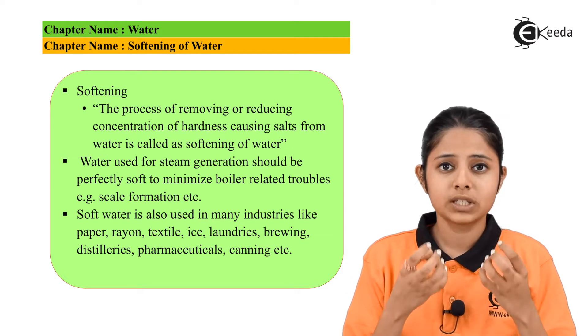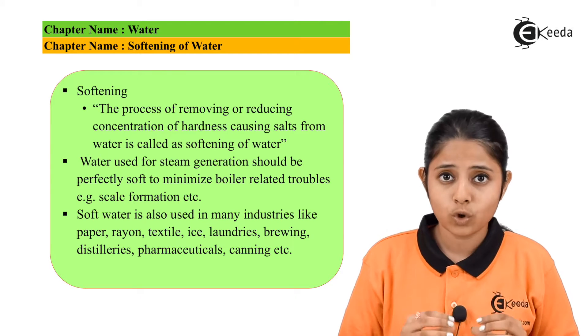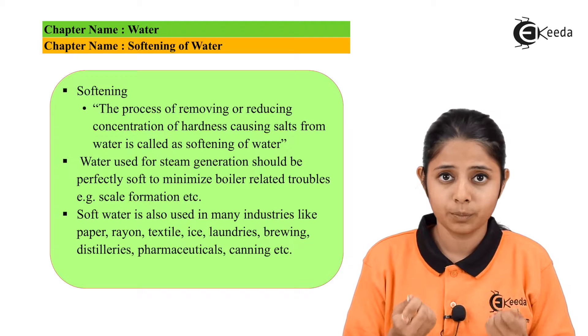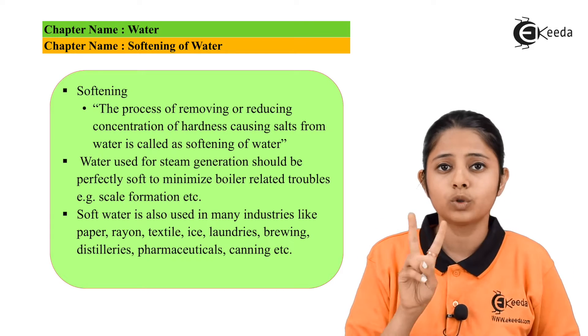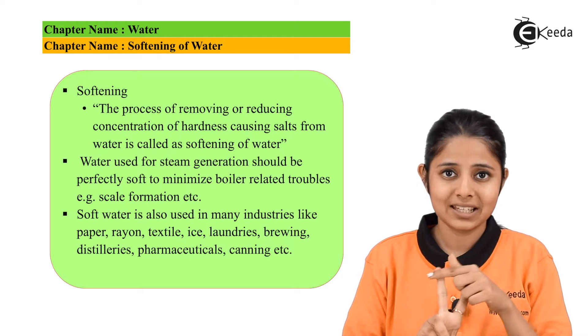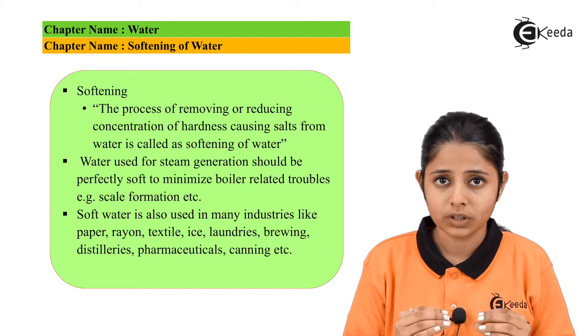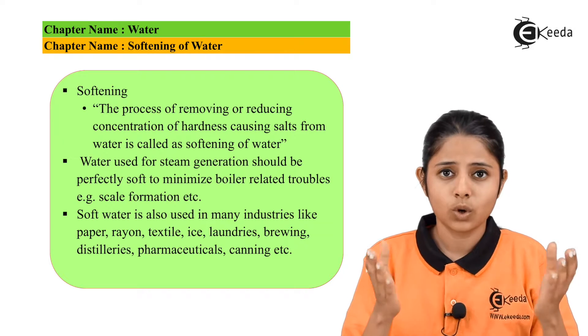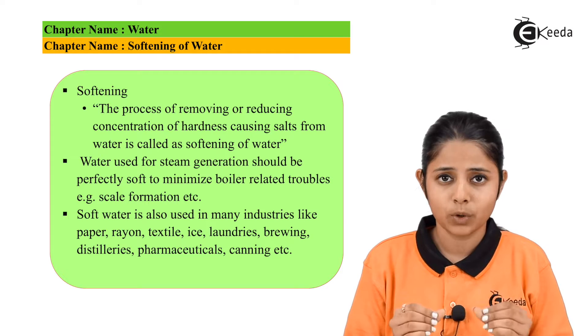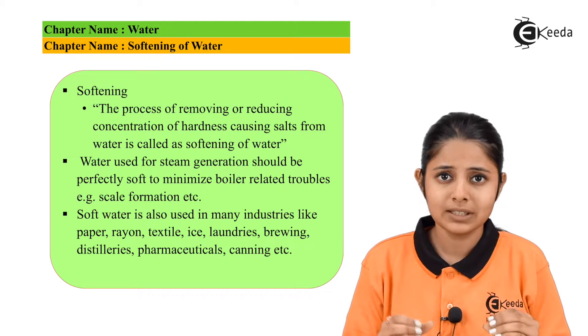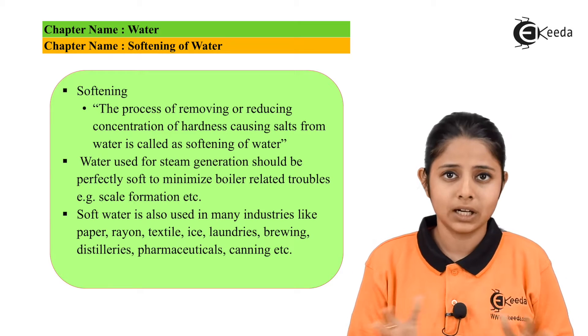Water used for steam generation should generally be soft water. If hardness-causing impurities are present in boilers, they will stick to the boilers and form scales and sludges. Scales and sludges are depositions of impurities inside our machines or boilers. Scales are hard impurities and sludges are mushy or soft impurities, but both are undesirable.